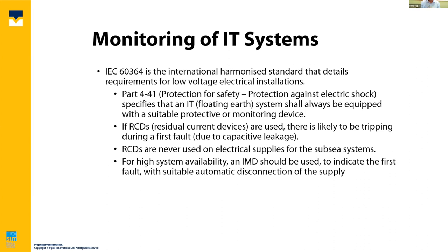Now, domestically or on the building site, you would just use a residual current device. That works on very short cables. However, as soon as you have capacitive leakage, which you do on a long umbilical, those RCDs will be tripping as soon as you turn the system on. So for that reason, RCDs are never used on electrical supplies for subsea systems. We always use what is known as an IMD, or insulation monitoring device.